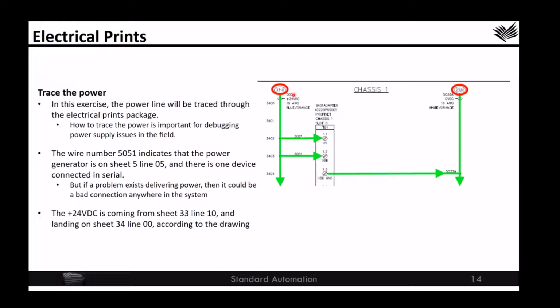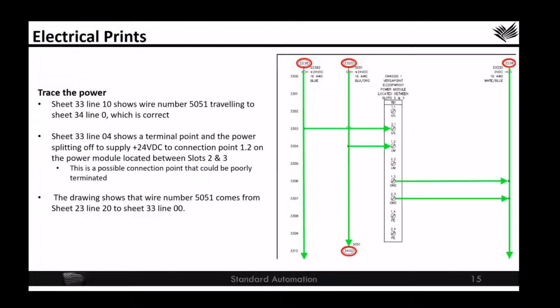So we see that the 24 volt power is coming from sheet 33, line 10 to sheet 34, line 00. Sheet 33, line 10 shows wire number 5051 traveling to sheet 34, line 0, which is correct. That's what we expect. Sheet 33 that we're on, line 4, also shows a terminal point and the power splitting off to supply the 24 volt DC power to connection point 1.2 between slots 2 and 3. This is a possible connection point that could be poorly terminated. Maybe there's a loose connection at this terminal, and that's an area that needs to be checked if you have power supply issues.